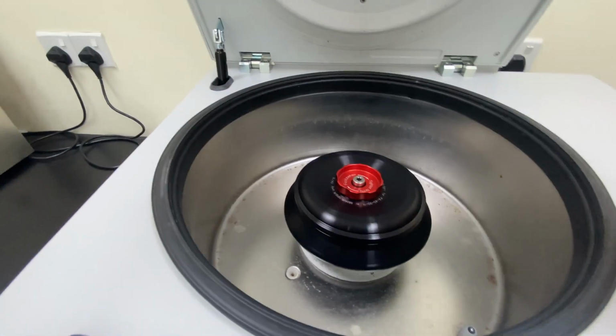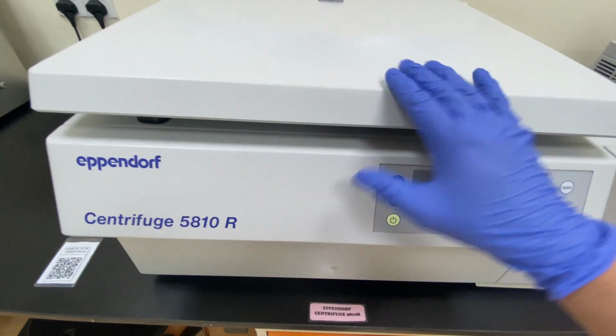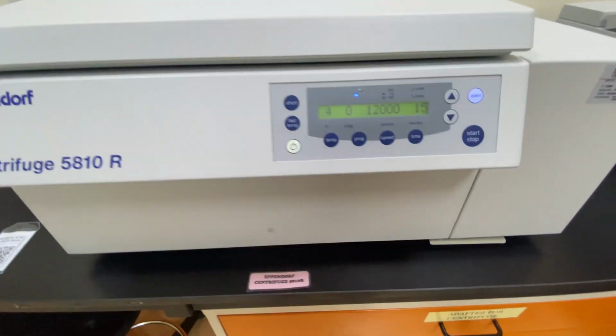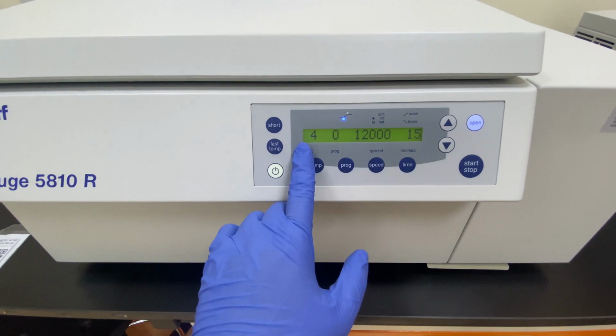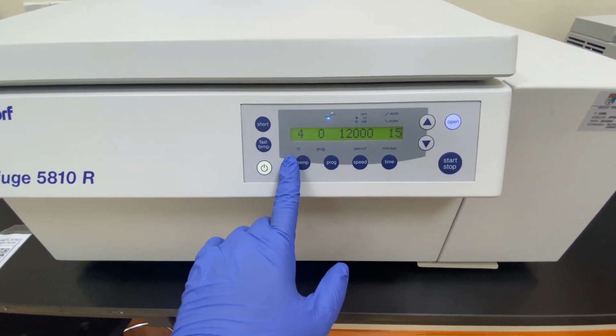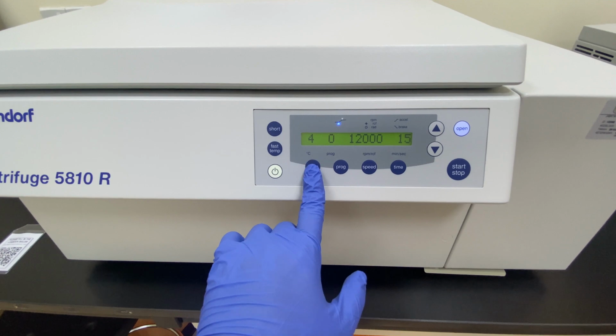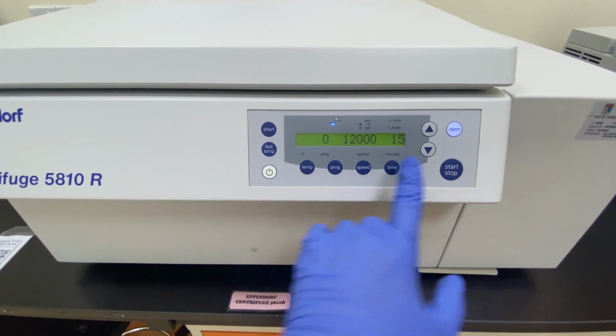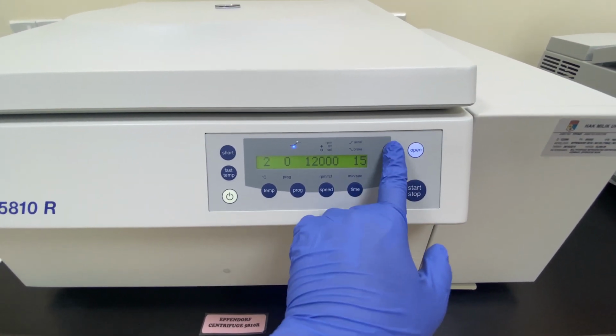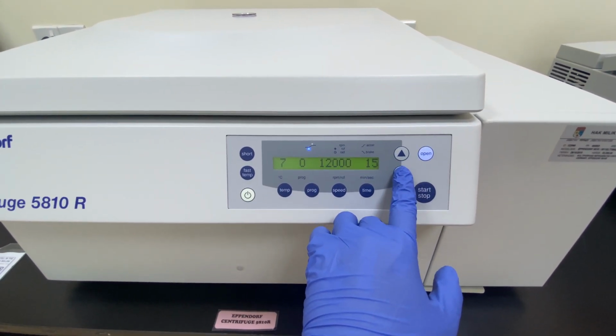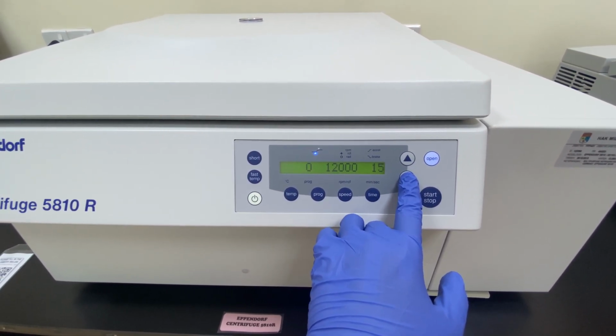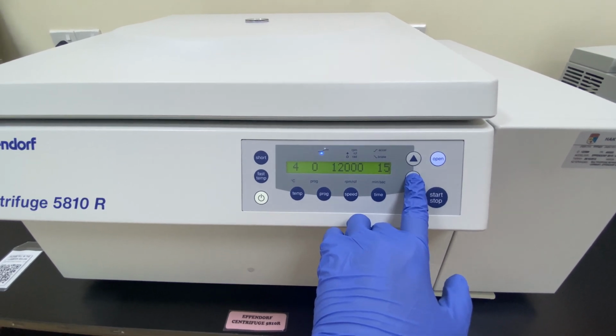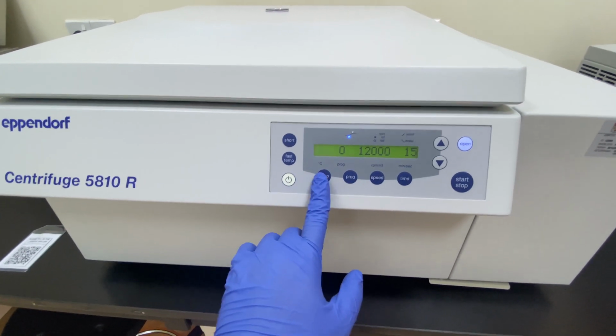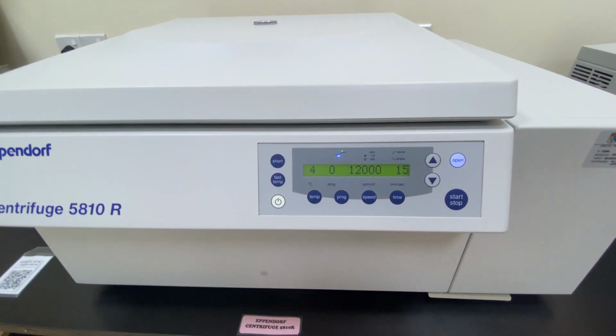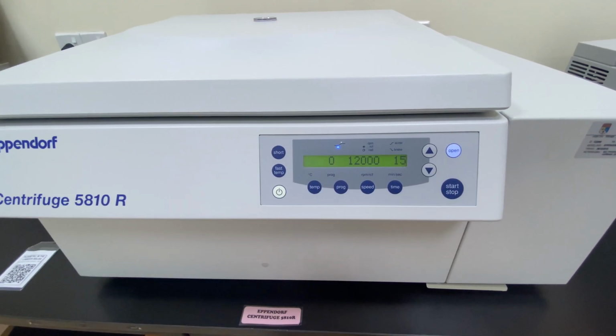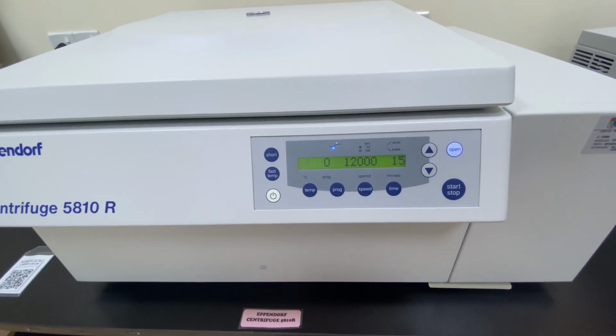But before that, if you want to change the temperature, you have to set this first. This machine is already set to 4 degrees, but if you want to change it, just click and press down to whatever temperature you want. We always need the standard 4 degrees; if we need something other than 4 degrees, we just use the other centrifuge.